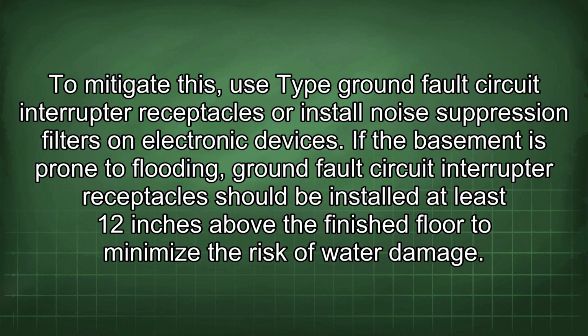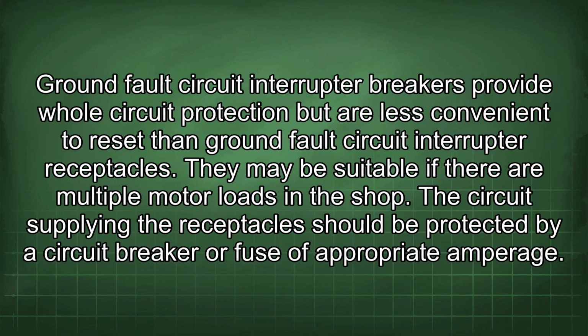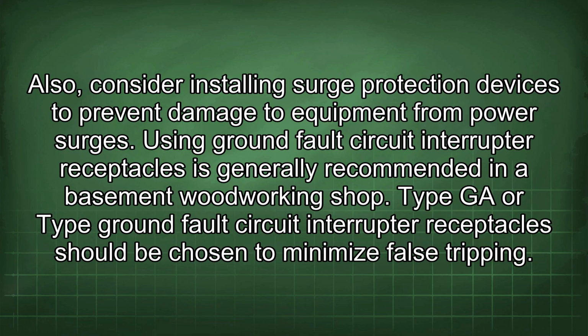If the basement is prone to flooding, ground fault circuit interrupter receptacles should be installed at least 12 inches above the finished floor to minimize the risk of water damage. Ground fault circuit interrupter breakers provide whole circuit protection but are less convenient to reset than ground fault circuit interrupter receptacles. They may be suitable if there are multiple motor loads in the shop. The circuit supplying the receptacles should be protected by a circuit breaker or fuse of appropriate amperage. Also, consider installing surge protection devices to prevent damage to equipment from power surges.